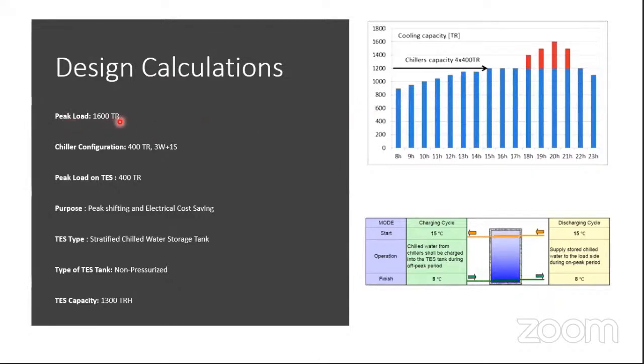The peak load is 1600 tons, and the chiller configuration is 400 tons, three working, one standby, and the peak load on thermal storage is 400, like we saw. The purpose here is peak shifting and electrical cost saving. You see, this is the load profile from the 8th hour down to the 23rd hour, out of which this was the connected load that was saved, and this much load was being taken care of by thermal storage.